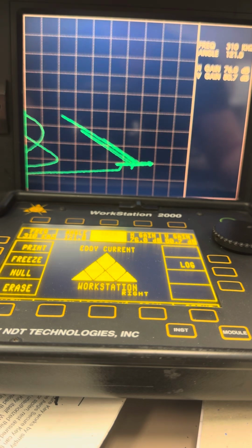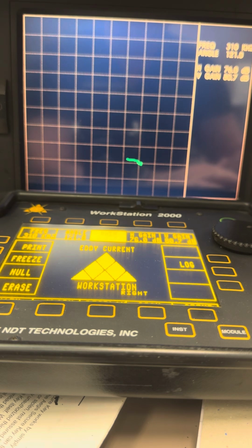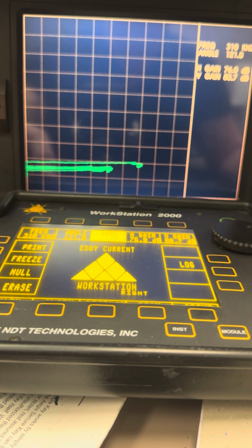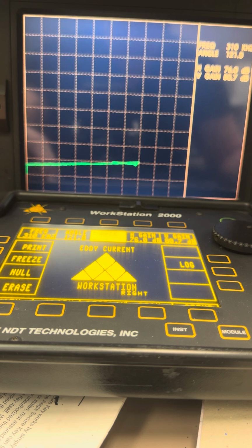First, we'll just see what happens to the operating point. The far right side of my screen there, that's the operating point for aluminum. And if I put 1 mil of non-conductive coating in there, see what a difference that made? That's like two whole divisions just from 1 mil of non-conductive coating thickness. That's with the coating, that's without the coating.